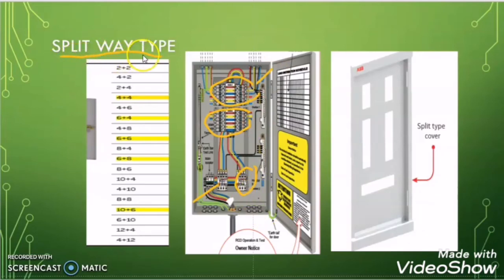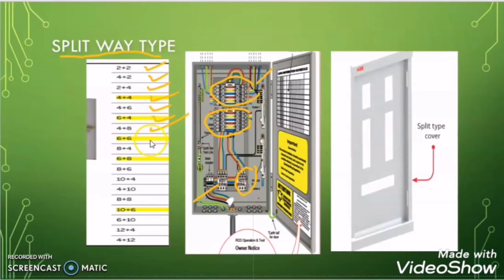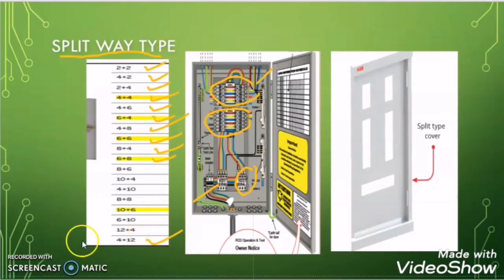But in the split way type DB enclosure, the outgoing breakers are divided into two sections. The first section is protected by one RCD device and the other section is protected by another RCD device. The split way type enclosure can be of 2+2, 4+2, 2+4, 4+4, 4+6, 6+4, 4+8, 6+6, or 4+12 way type.